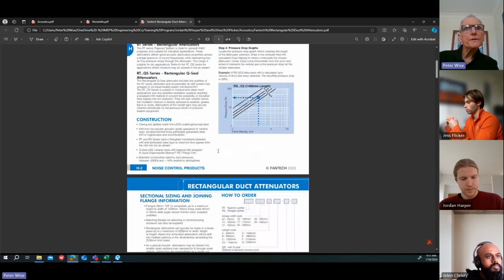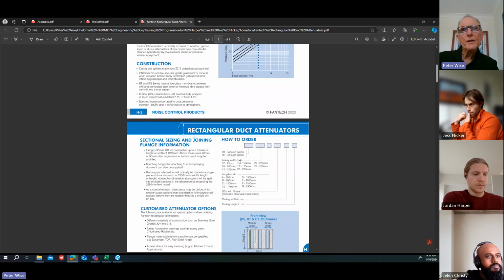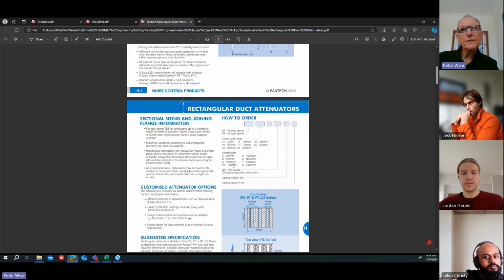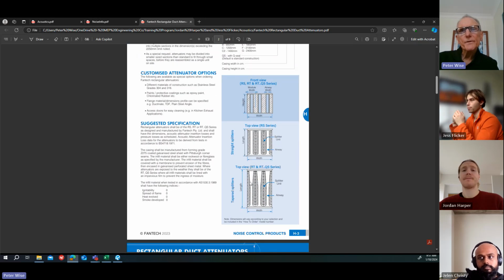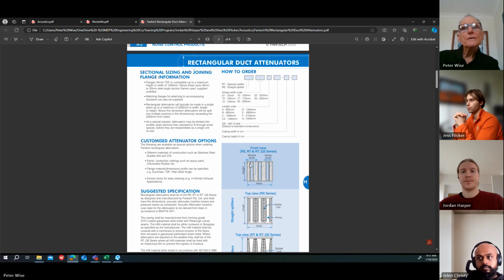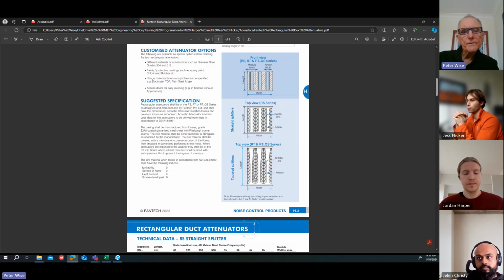So with those codes that are given here, the airway width code 07 is 75 millimetres, 10 is 100 millimetres, and so on. So that's the airway width through the attenuator. As those airway widths increase, that's going to help to reduce the passage velocity through the attenuator. So if you're working on a constant 5 to 6 metres a second face velocity, then as those airway widths increase, the passage velocity through the attenuator will reduce, and the pressure drop will reduce as well.